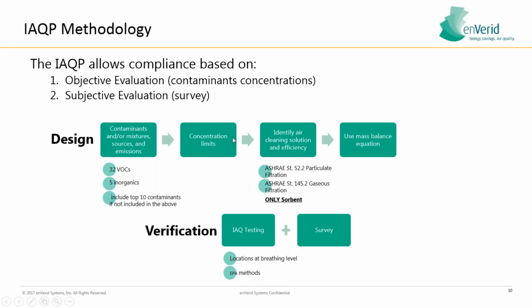Now, this is one part of the indoor air quality procedure which has led to some pause amongst the MEP community, saying, I'm not a hygienist. I don't know what the concentration limit should be within a space. ASHRAE has now provided some guidance on this. You know, formaldehyde should not exceed 33 micrograms per meter cubed, et cetera, et cetera. And LEED also has published limits as well. So you can reference both of those for concentration limits within certain spaces, very similar to how you would reference other tables within ASHRAE. Then you identify an air cleaning solution and its efficiency.